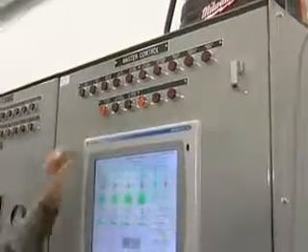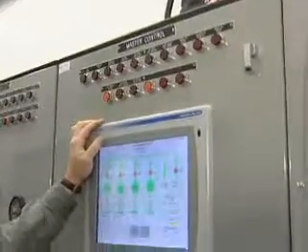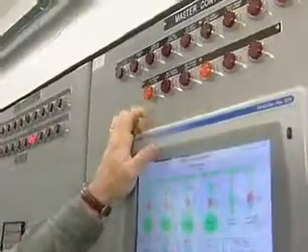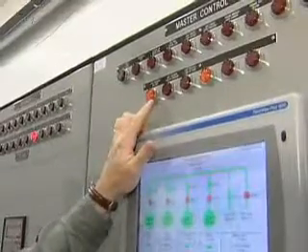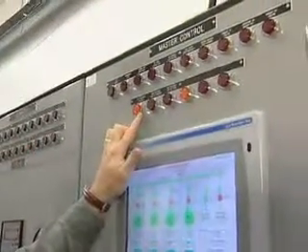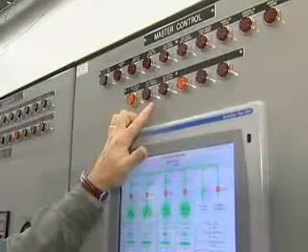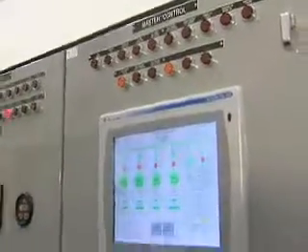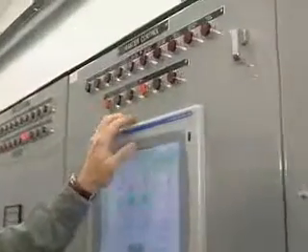From there we go to the heat recovery section. We can tell which direction the flow is. Heat recovery with no load typically means the system is down and not running properly. Loss of pressure means we have a leak and it needs to be repaired and pressurized back up. Loss of flow — we have two flow indicators on our loops that tell us our circulating pumps are working correctly and moving fluid. If they're not working, that light will be on. We also have three spare lights that give us options to add other functions to the switchgear.